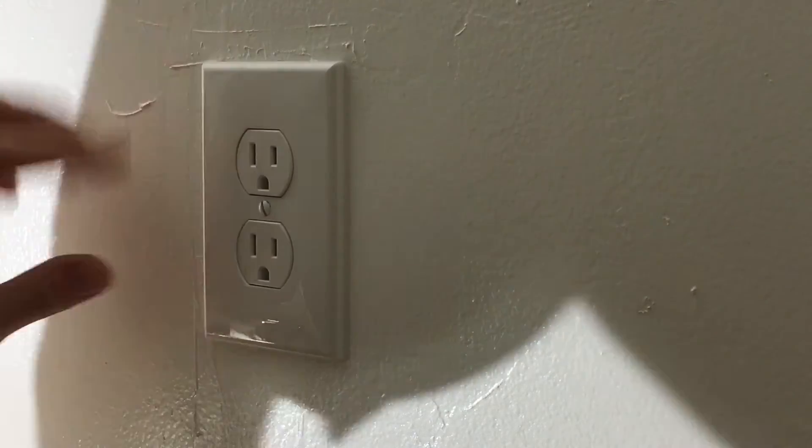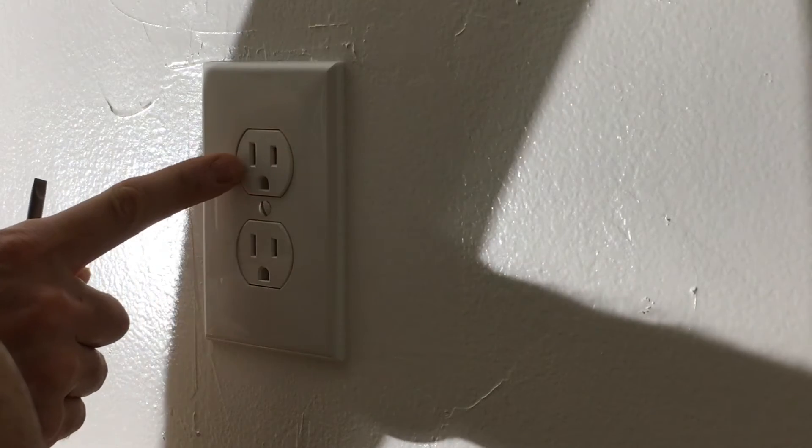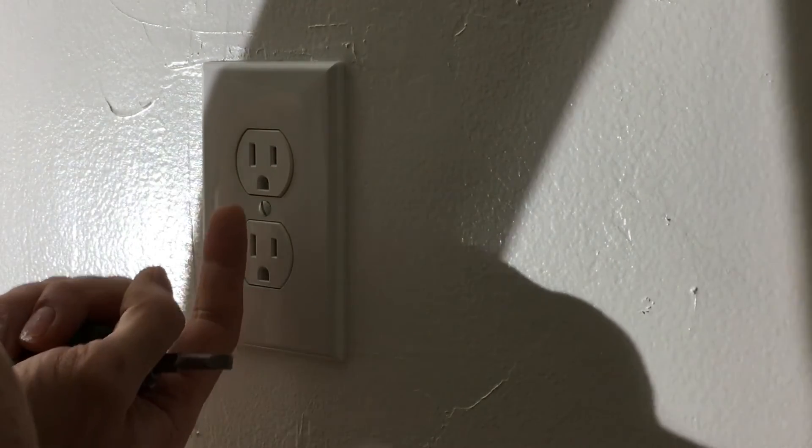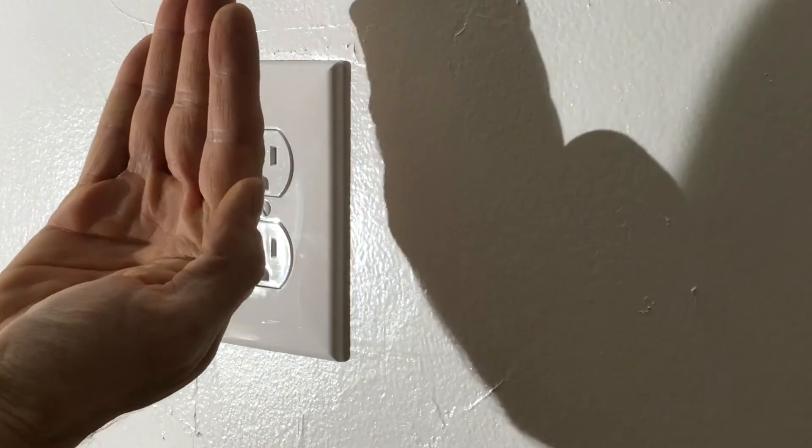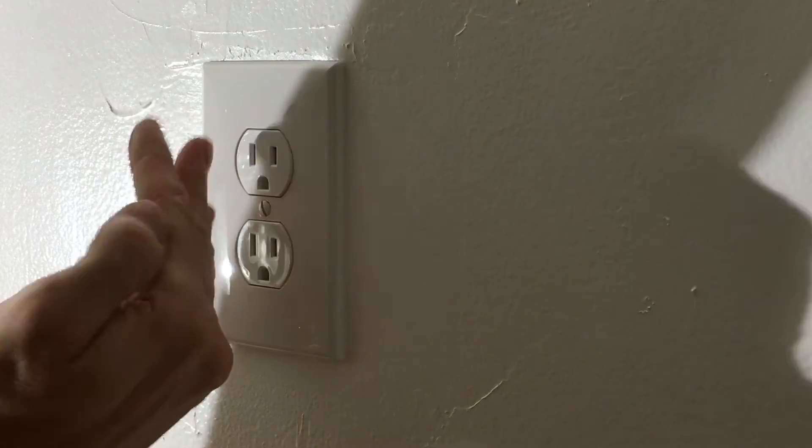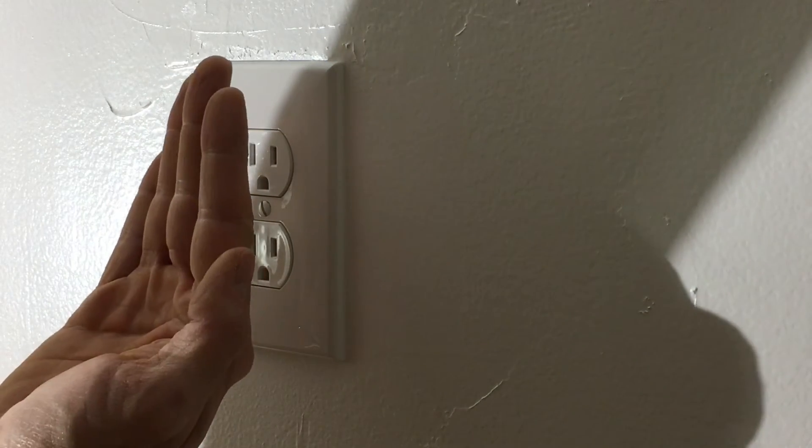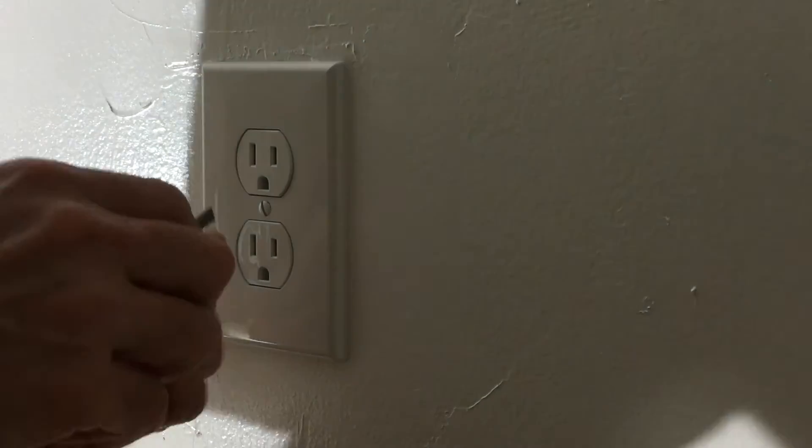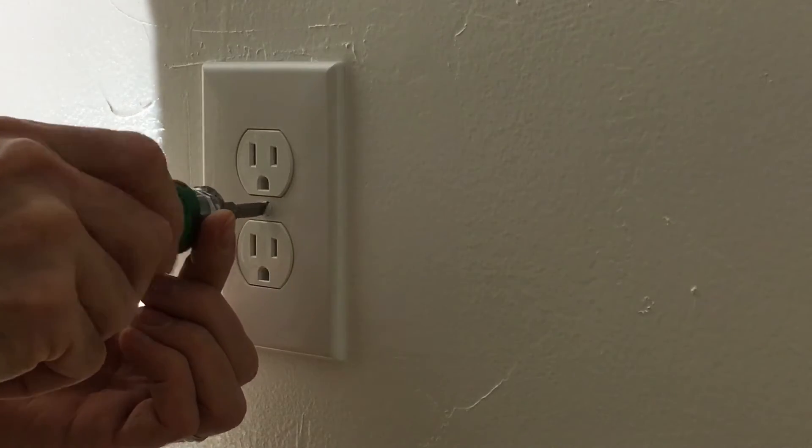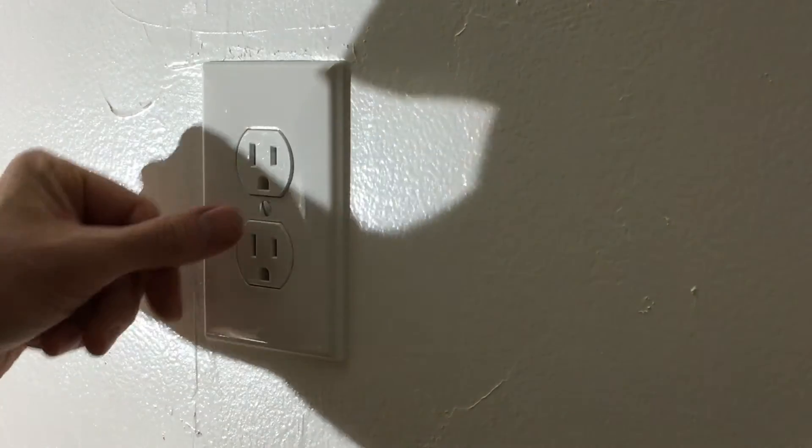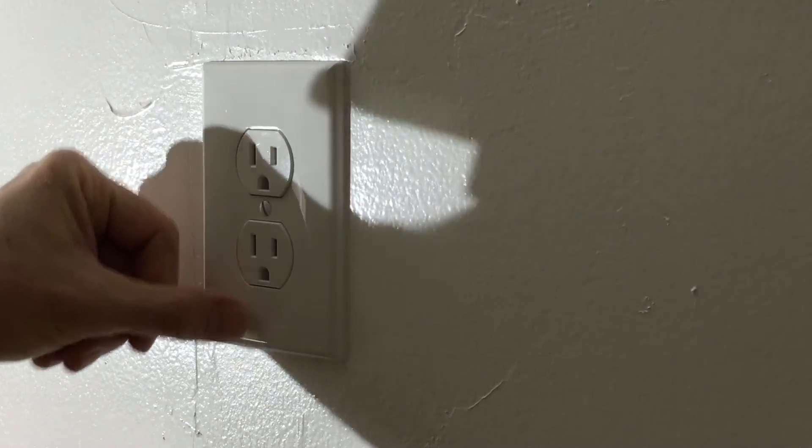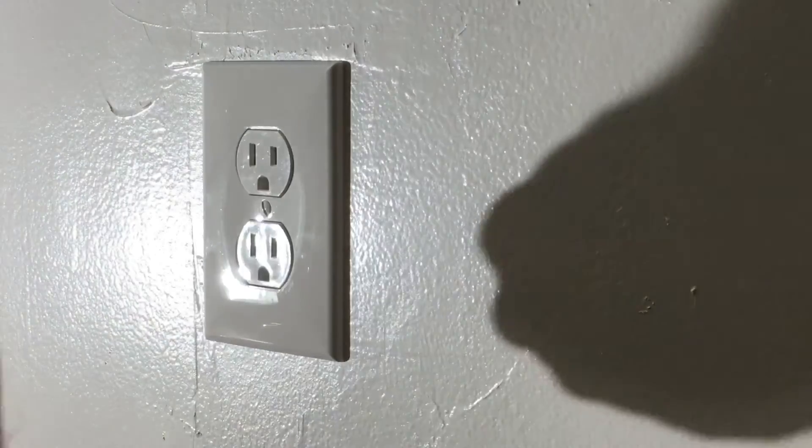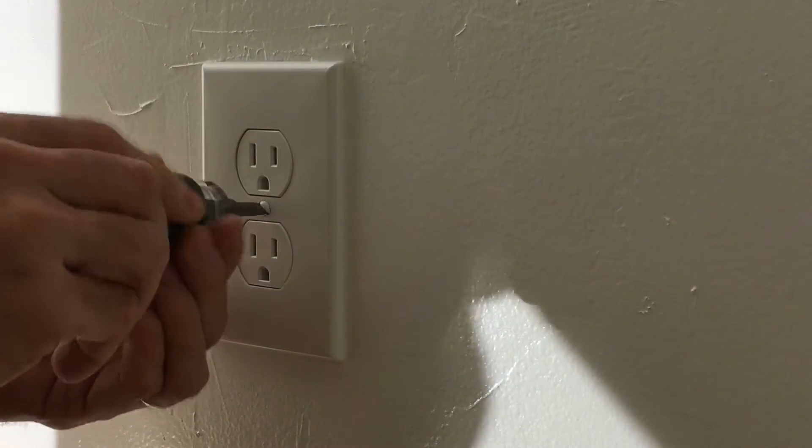Okay, so on this one you can see that the outlet itself is kind of at a little bit of an angle. I think that's because all the wiring back there was so tight. Either the box is a little bit more on this side than this side, or the outlet because of the wiring it's a little bit angled. And I can tighten this down, but you can still see that this side is sticking out more than this side over here. It still doesn't look horrible, it looks way better than it did, but in order to fix this...